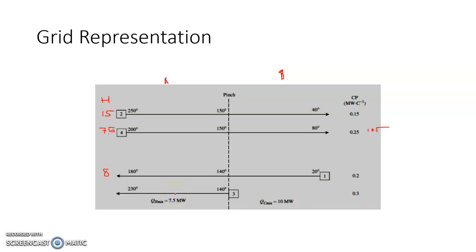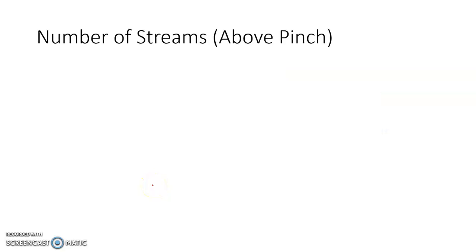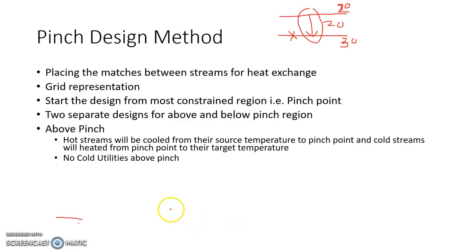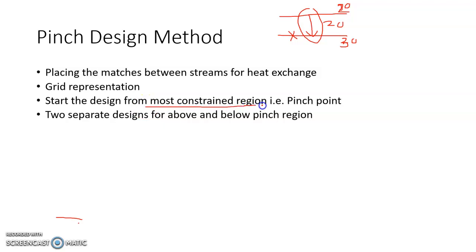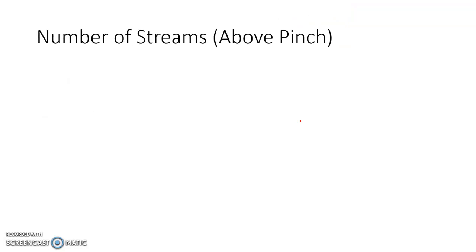This is how we represent streams on the grid diagram, and we'll explore this further when designing the network above and below the pinch. An important aspect of designing is that we concentrate on the above pinch region and start the design from the most constrained region, matching pairs of streams which are at the pinch point. As you move away from the pinch point, the temperature difference between streams generally exceeds ΔT minimum, giving more design freedom.